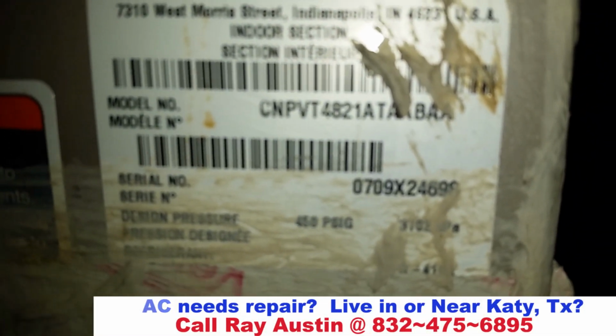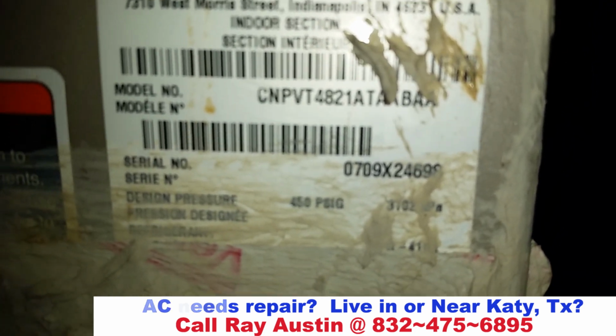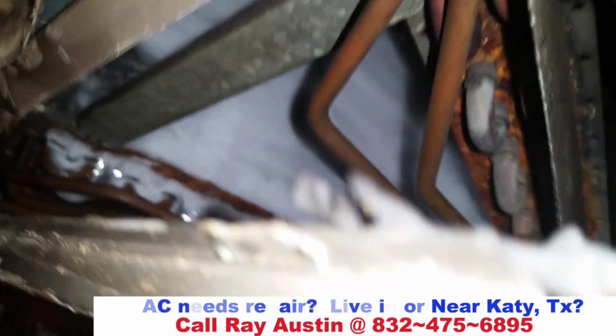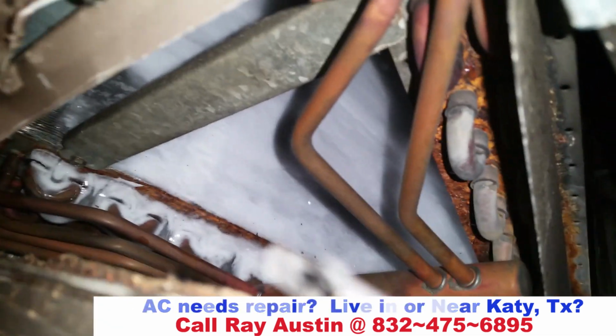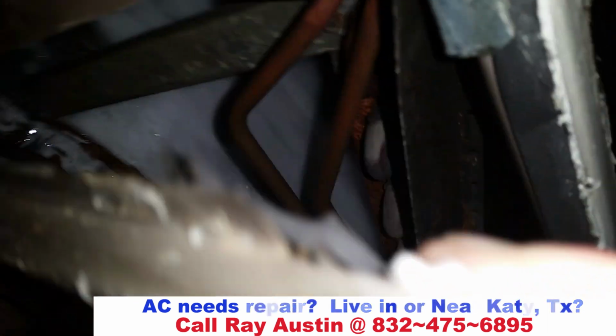So I initially get this AC call as AC no cool. This is the indoor equipment. The coil that sits on top of the furnace is manufactured in 2009. And so I open up the coil box to discover a frozen coil. From this point on, I've got to determine why that coil is freezing up, because certain things can mimic this symptom, and so I've got to try to find out why this coil is freezing up.